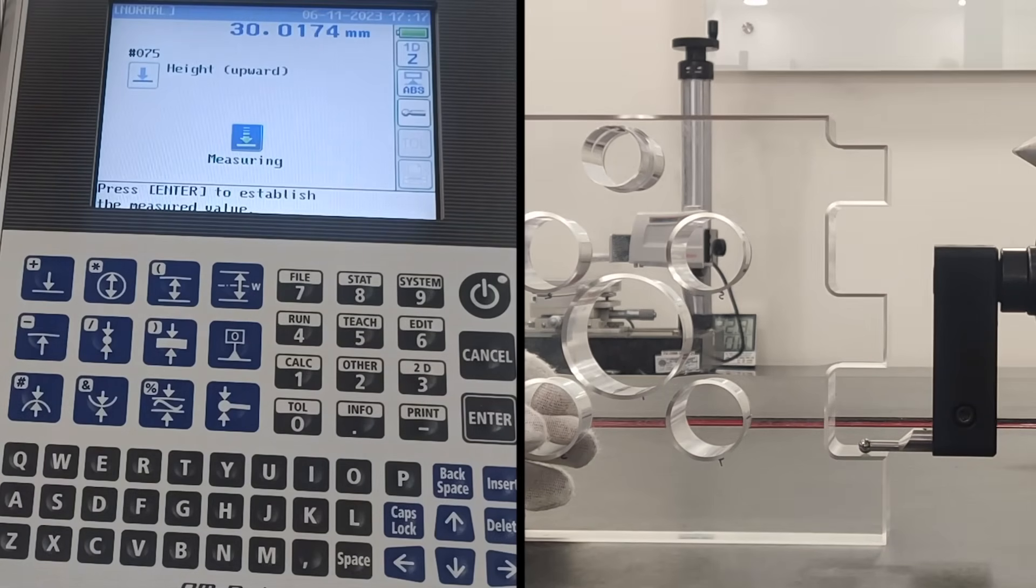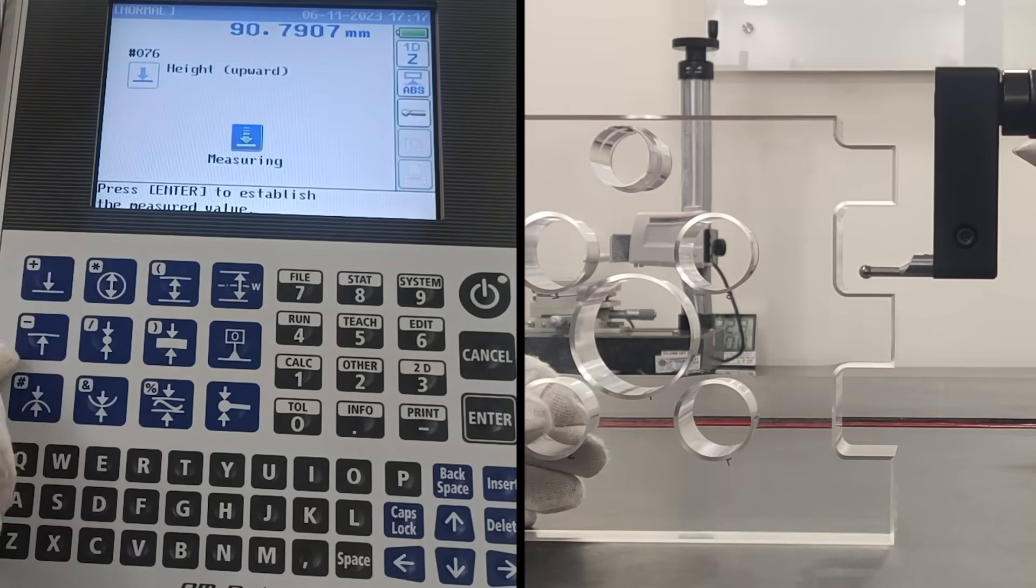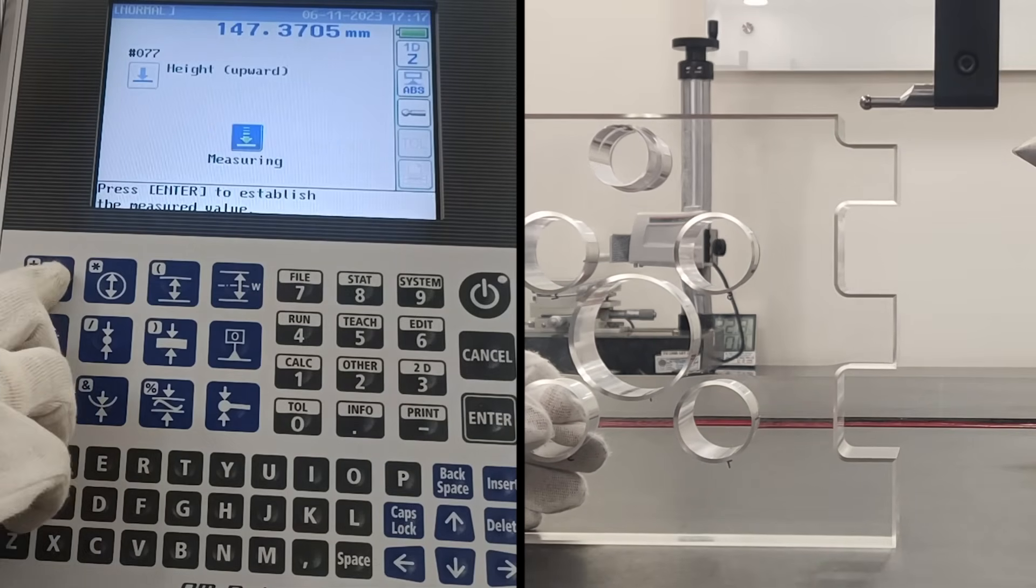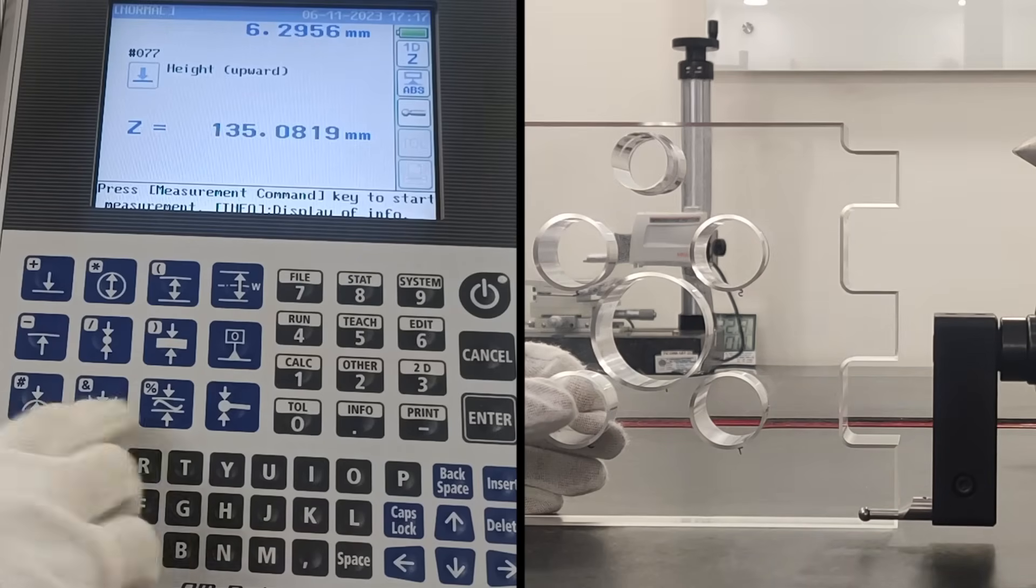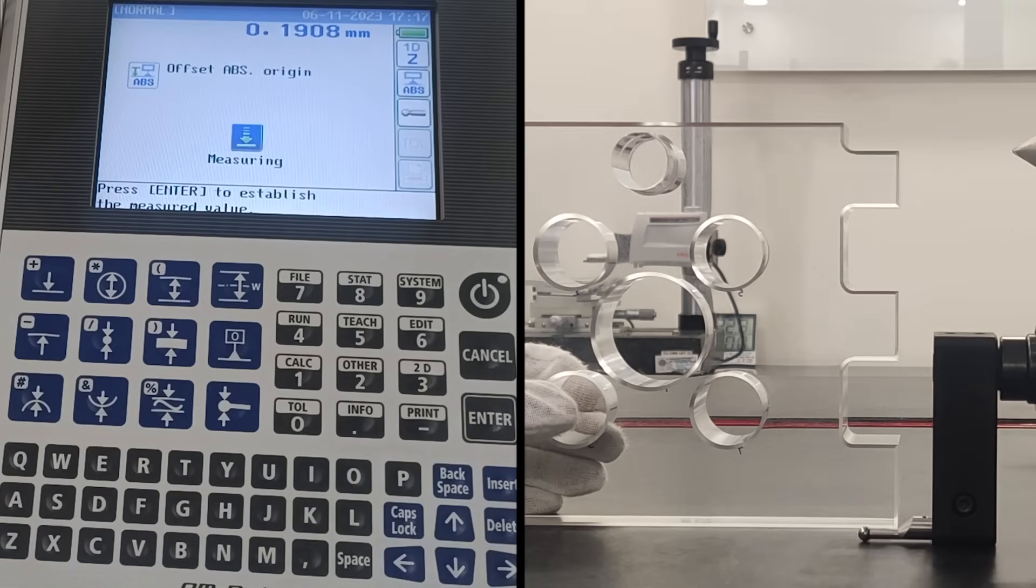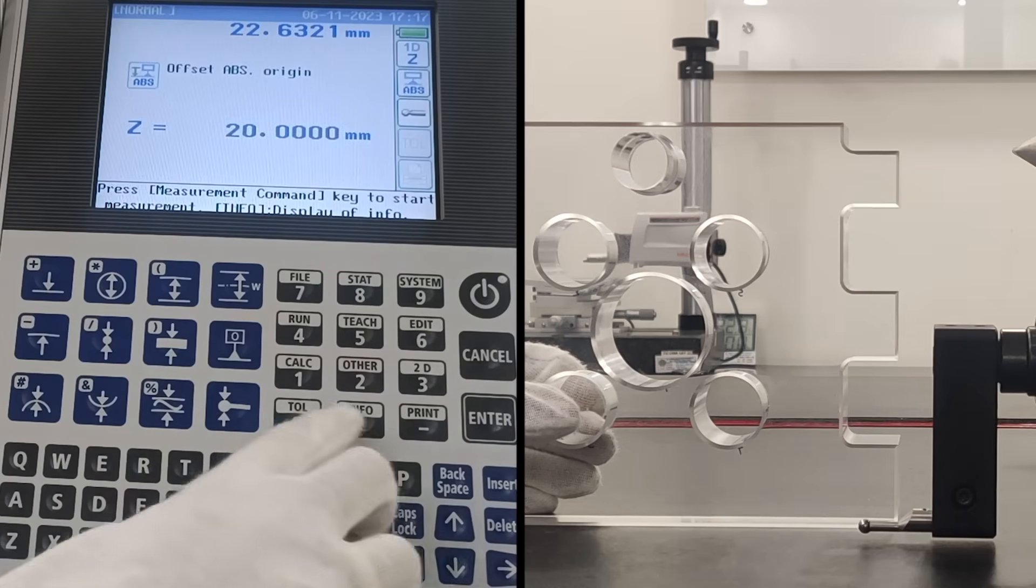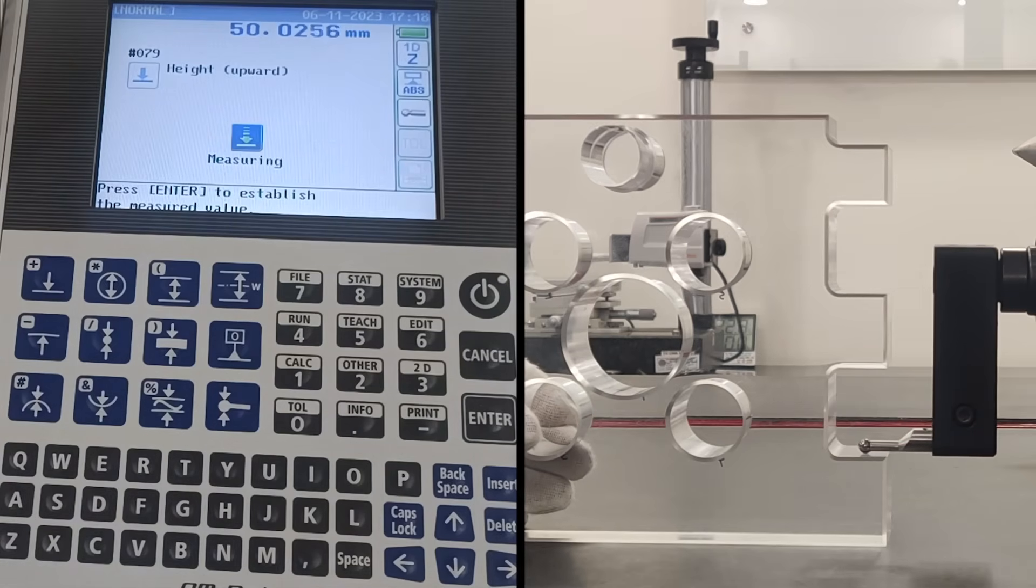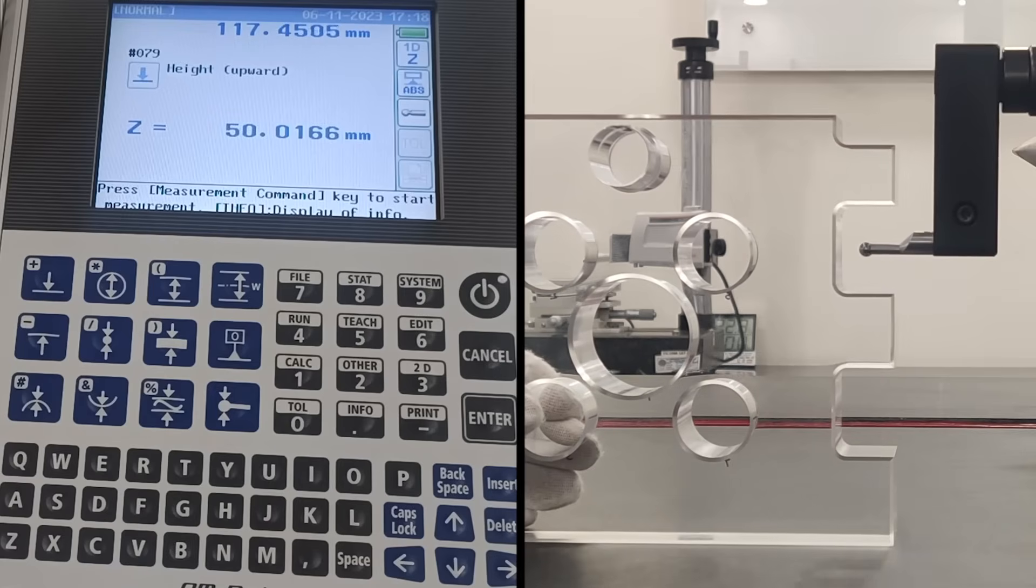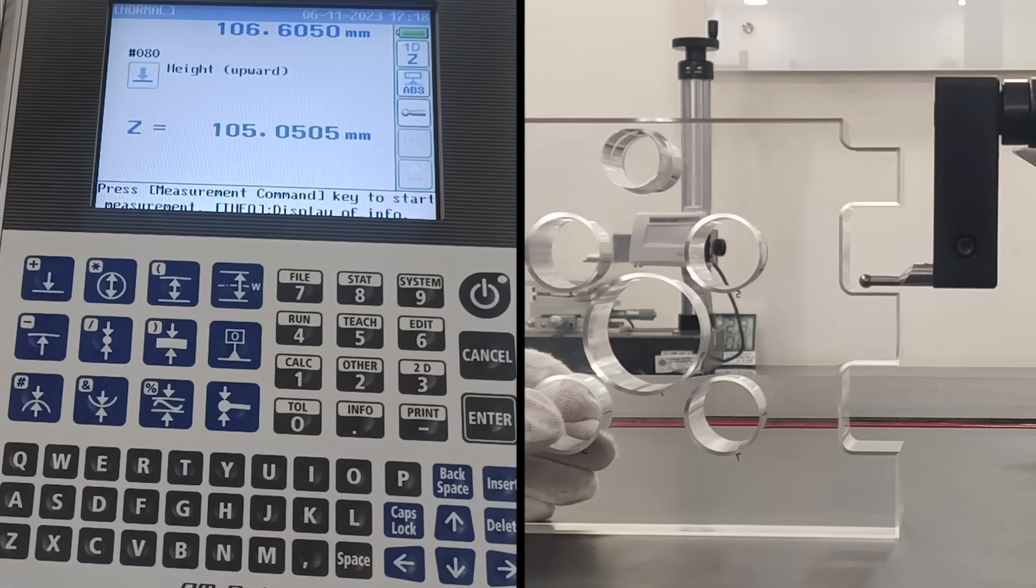Let's measure each step height. It reaches 30 mm. The second step measures 85 mm. And the third step measures 135 mm. Now set the offset origin value. We'll set it as 20 mm. We shall again re-measure the heights. The first step reads 50 mm. The second step reads 105 mm.